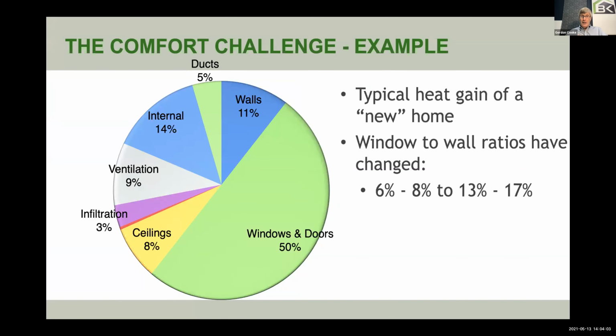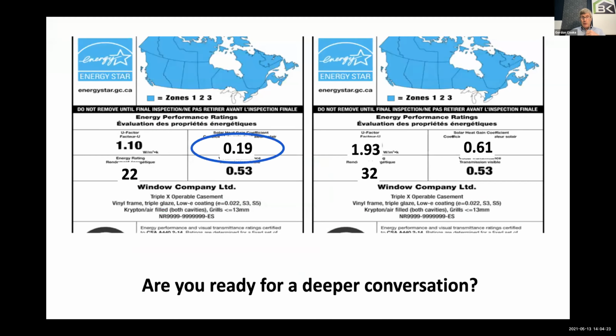But remind ourselves that with windows and doors, the issue is we put more windows in houses. And over the last 30 years, we've basically doubled the windows in houses. We used to be at about 6 to 8% window to wall ratio. Now we're at 13 to 17%. And it has a huge impact on cooling loads, is what we need to get to. And you've seen this before. There's kind of the range of choices you can get. And you can get anywhere from about a 0.19 solar gain to a 0.61. 3 times the solar radiation.